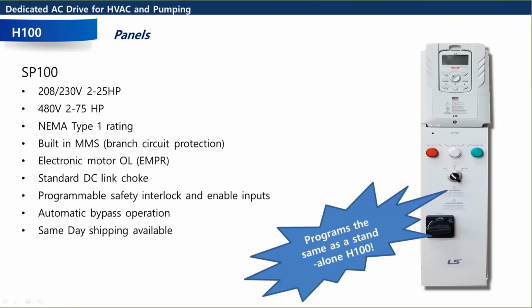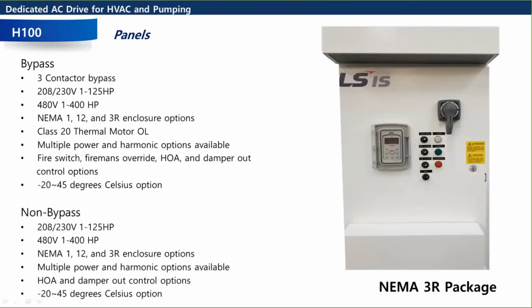And it's just an H100 on a mechanical bypass. So if you could program an H100, if you want any of those features we just talked about, it's all there. You just have to program it. So pretty easy. We are also offering some standard panel solutions too. So we can do 3-contactor bypasses up to 400 horsepower. NEMA 1, NEMA 12, NEMA 3Rs are the options. And we have a few different options like reactors and DC link chokes and stuff like that. HOA switches, temperature options. And then we have a non-bypass option as well. The non-bypass is available, same thing, up to 400 horsepower, and HOA switches and all that good stuff. So feel free to inquire about that if you ever have an opportunity come up.